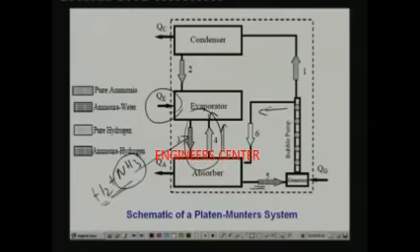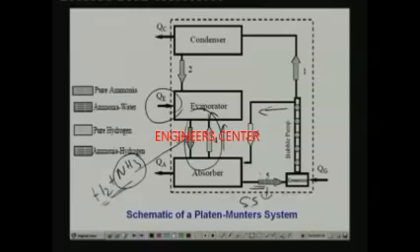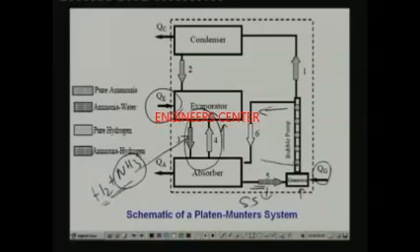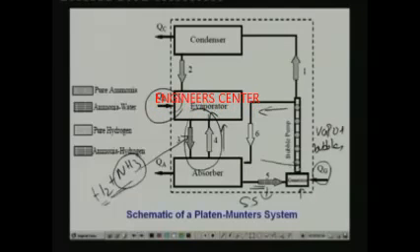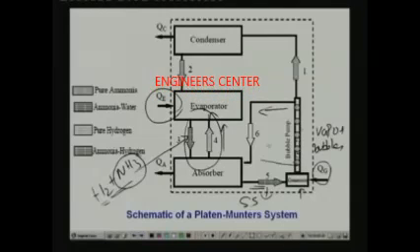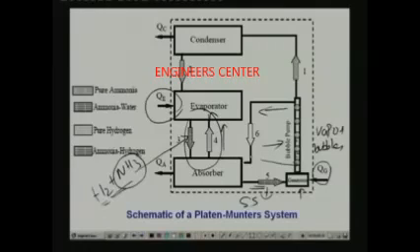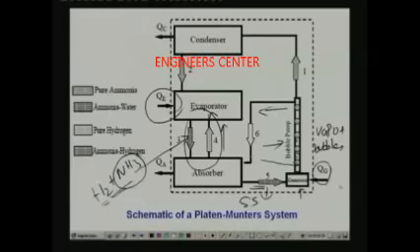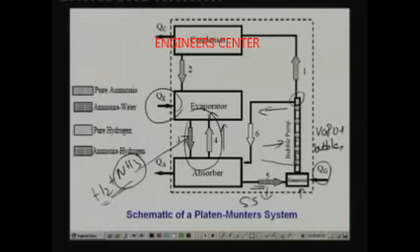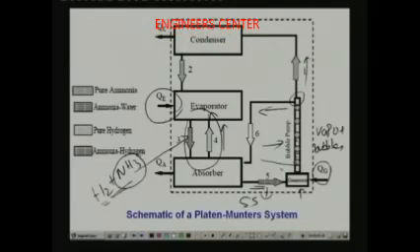The solution, now stronger in ammonia, is at 15 bar and goes to the generator where heat is supplied. Vapor bubbles are generated and move upward due to buoyancy, carrying some liquid along with them - that is the function of the bubble pump. The vapor bubbles move liquid from the bottom to the top due to buoyancy. At the top of the bubble pump, liquid goes down due to gravity and vapor moves up due to buoyancy - that is how the whole system works.